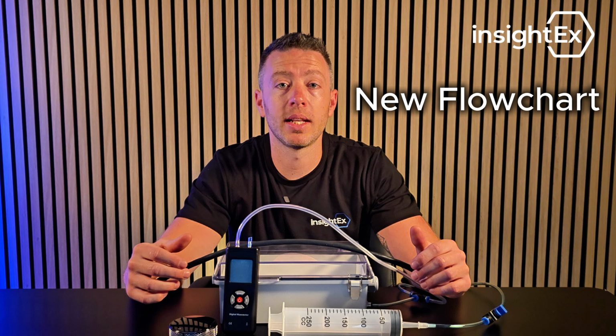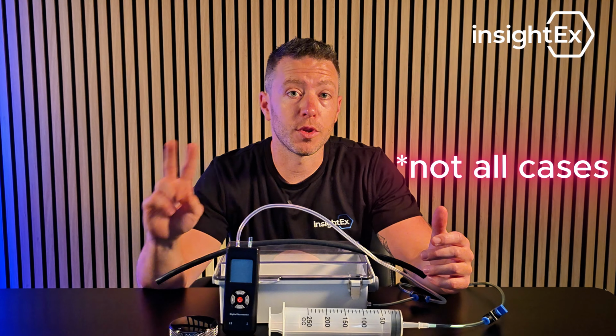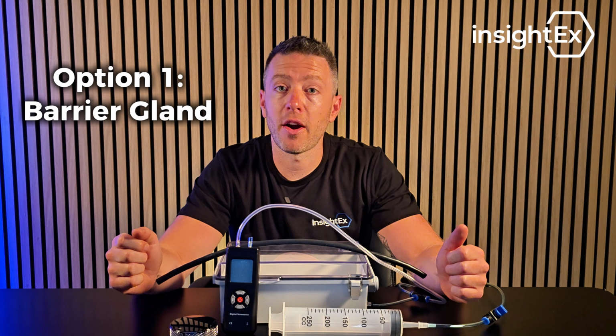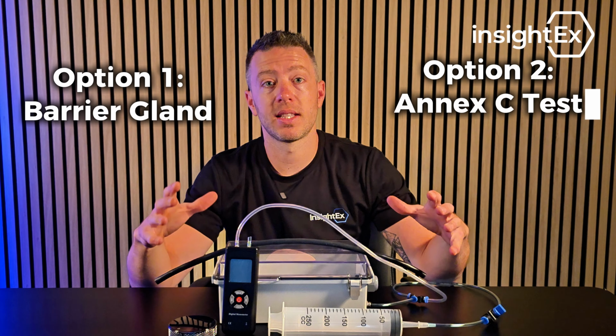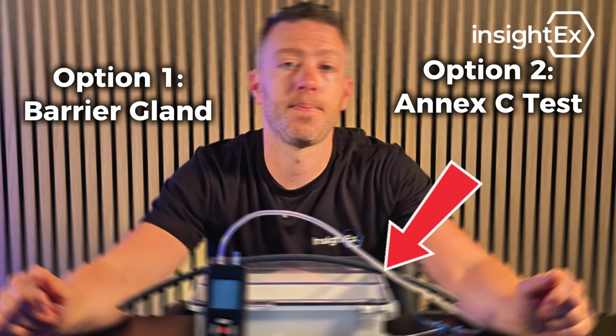In the new standard, you follow a specific flowchart to determine the right type of EXD cable gland. And in many cases, you'll end up with two options. You either install a barrier gland or you carry out this Annex C pressure test.